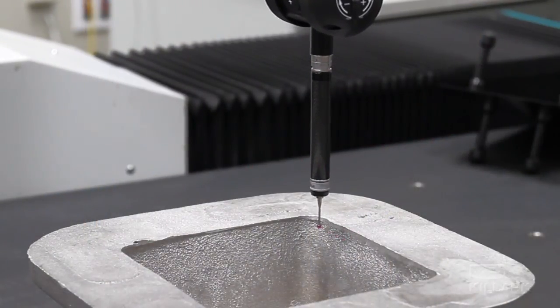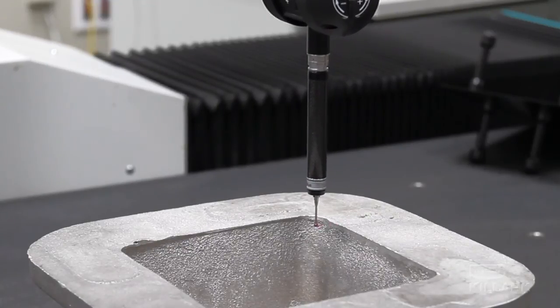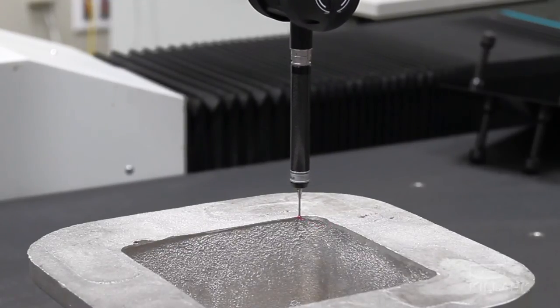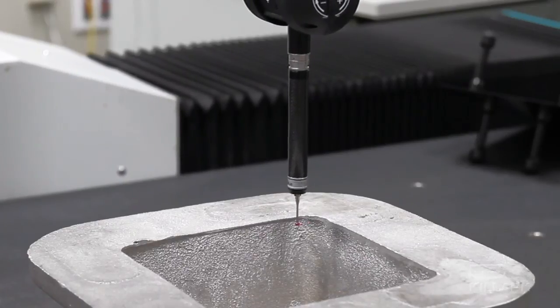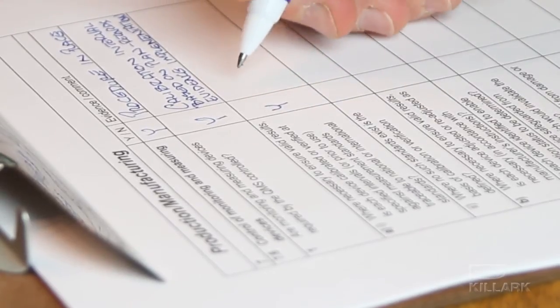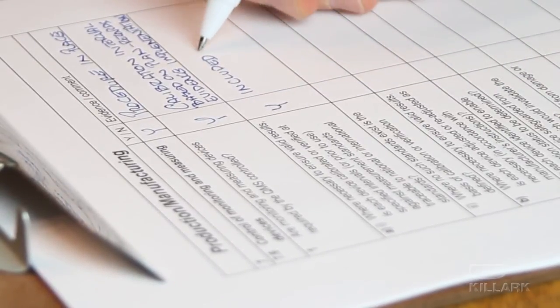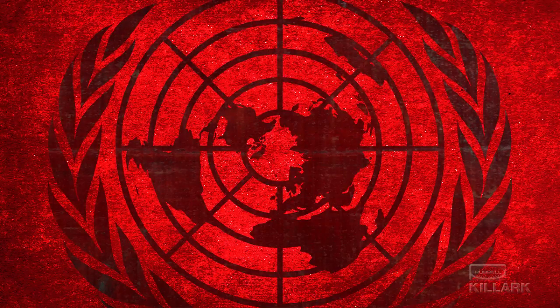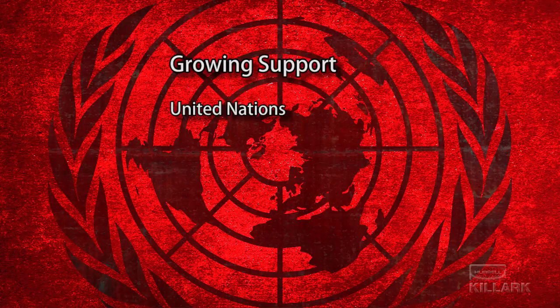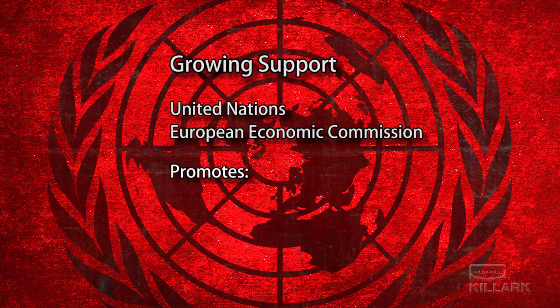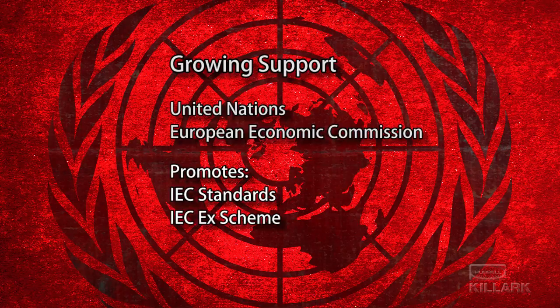The notified bodies would also conduct evaluations of the manufacturer's quality systems and controls, including the scrutiny of follow-up audits. The all-important test reports and certificates of conformity issued by these agencies provide the documentation for product nameplates and marking. Support for global harmonization continues to grow. The UN, through its Economic Commission for Europe, promotes and encourages adoption of IEC standards and the IECEx certification scheme among the Commission's 56 member countries.